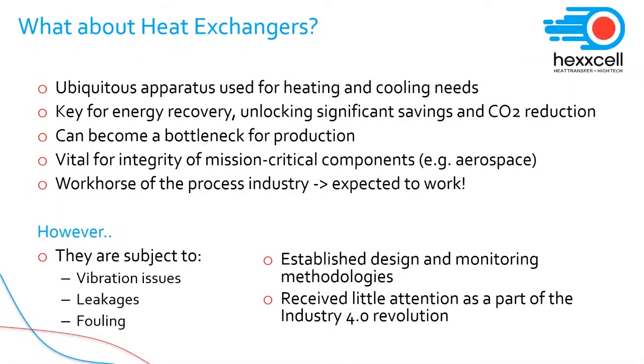Heat exchangers are everywhere in the process industry, and they're used for heating and cooling needs. They are instrumental for energy recovery, which enables plants to unlock significant savings. They are considered the workhorse of the process industry, and as such, they're expected to just work. However, they can become a serious bottleneck for production, as they are still subject to the same issues such as leakages, vibrations, and crucially fouling, as they were after the first industrial revolution.